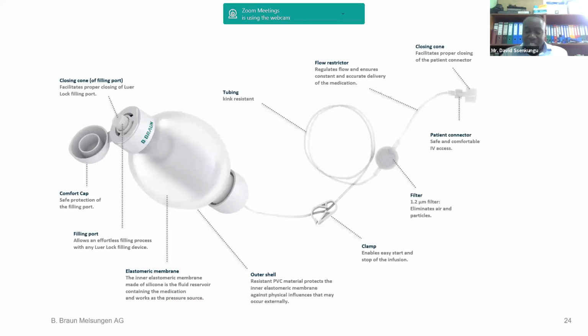If we look at the elastomeric pumps we offer, these are the different features of the pumps. We have a closing cone that facilitates proper closing of the Luer-Lock filling port. We have a comfort cap for safe protection of the filling port. Then we have the filling port, which allows an effortless filling process with any Luer-Lock filling device. We have the elastomeric membrane, the inner membrane made of silicone, which is the fluid reservoir containing the medication and works as the pressure source. Then we have the outer shell, a resistant PVC material, which protects the inner elastomeric membrane against physical influences that may occur externally.